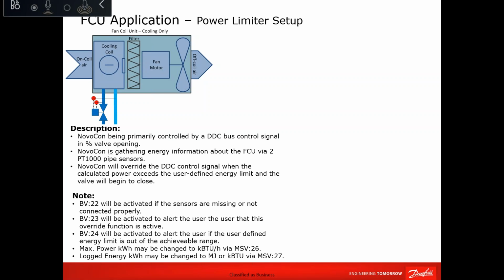So how will the power limiter setup be? Novocon is primarily controlled by the DDC on percentage of valve, which means the feature we are talking about, when we say that it can control the power, is a completely different feature from the normal control. Novocon can still be controlled normally like any actuator with a 0 to 10 volt signal, 4 to 20 milliamps, or from the BMS. And this power limitation feature is something extra, a different variable addressed to the actuator. It will not interfere with the normal operation of the actuator if you don't want it to.